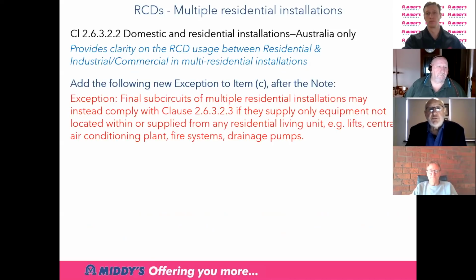Okay, this is to do with RCDs in multiple residential installations. We've had a lot of queries about where's the demarcation in an apartment building, a block of units, almost hotel type accommodation, when you're talking about application of an RCD. So in domestic or residential, we're talking about 30 milliamp RCDs on all final subcircuits. When you're talking about industrial, it only covers final subcircuits up to and including 32 amp. And also within that, there's a number of exceptions that can be applied. I think there's 6 of those that can be applied.